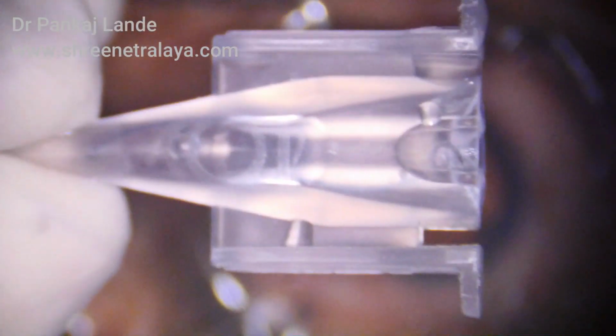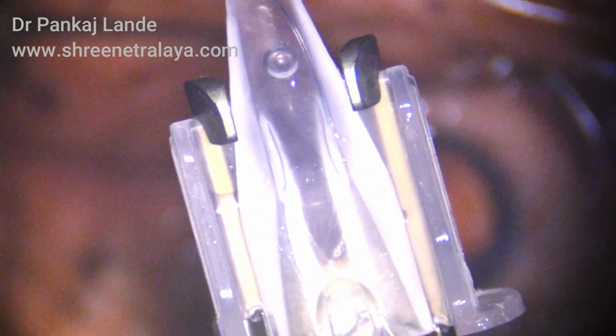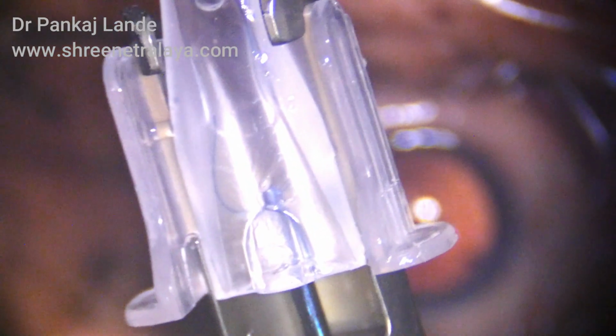Now you can load this cartridge into the injector system. You can observe the cartridge under the microscope and note that your leading haptic is straight and trailing haptic is straight. Here I have locked the cartridge into the injector and I will push the plunger slightly, and here you note, as soon as I push my plunger, the trailing haptic is getting engaged in the plunger.